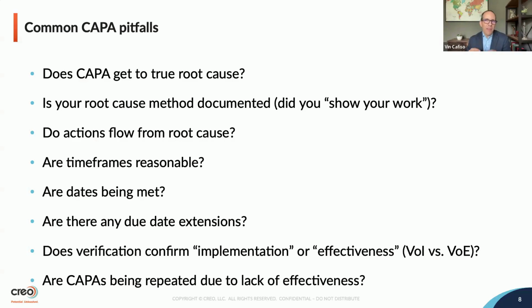It may be that your 483 CAPA was effective because we didn't have anything happen within 3 months after implementation. But then you have two CAPAs on the books which are essentially something to do with internal audit, right? You're like, hold on, wait, there was a 483 for internal audit. So now what's happening? You definitely want to avoid that, and that's why effectiveness is so important, to make sure that you really get to root cause. That's the only way you get to effectiveness. If everything in the middle is connected, effectiveness is just a foregone conclusion.